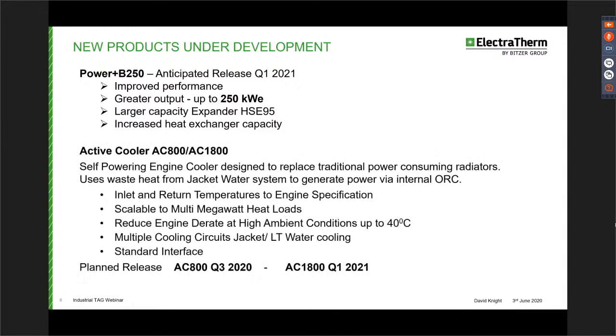Second product line, which is quite exciting, is the new active cooler. The new active cooler is a self-powering engine cooler, which is designed to replace traditional power-consuming radiators. It uses the waste heat from the jacket water system to generate power via an internal ORC. So it uses the inlet and return temperatures to the engine specification. Scalable, it will reduce engine derate at high ambient temperatures. We do multiple cooling circuits: the jacket water, low temperature water cooling, the standard interface. Our first unit is due to be released later this year with a larger unit early next year.